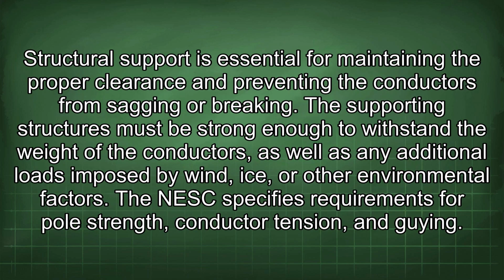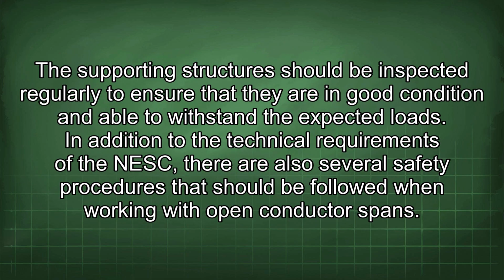Structural support is essential for maintaining the proper clearance and preventing the conductors from sagging or breaking. The supporting structures must be strong enough to withstand the weight of the conductors, as well as any additional loads imposed by wind, ice, or other environmental factors. The NESC specifies requirements for pole strength, conductor tension, and guying. The supporting structures should be inspected regularly to ensure that they are in good condition and able to withstand the expected loads.